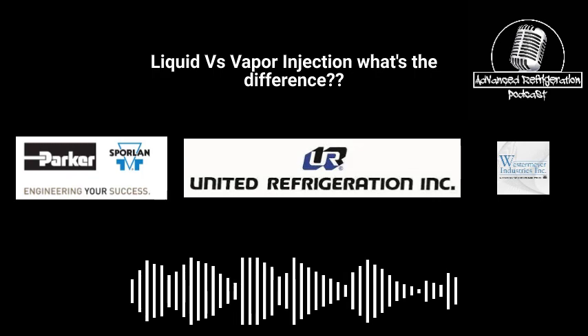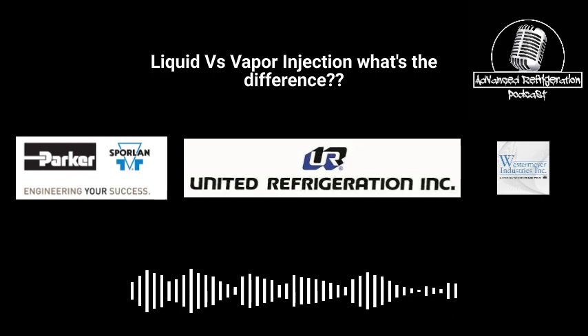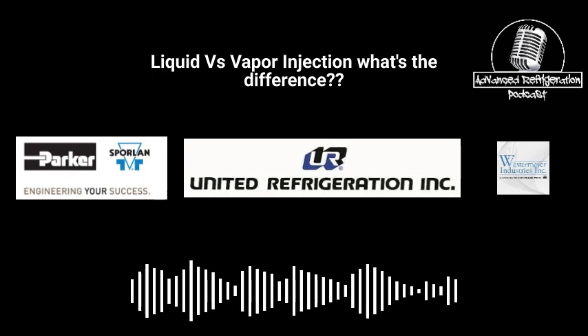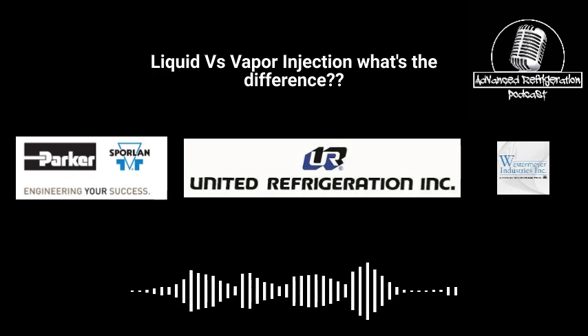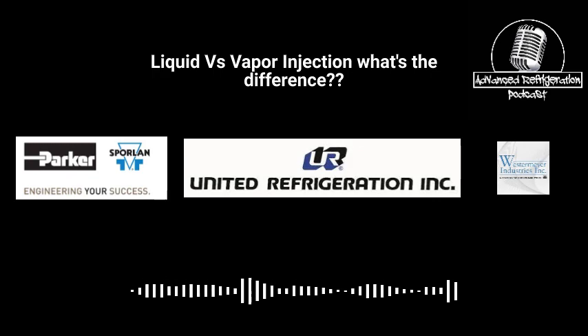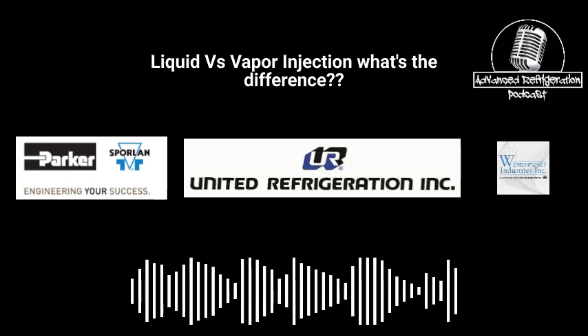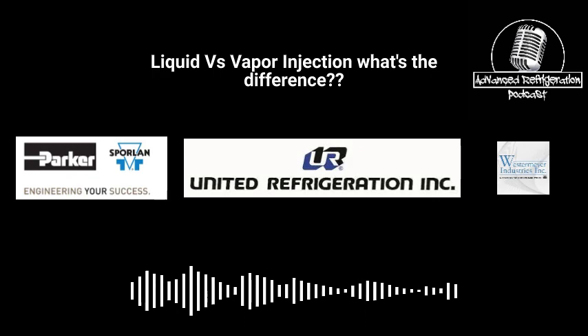So when you're having to rebuild that vapor injection, if you do not have an isolation line before that, isolate that whole compressor, pump it completely down to atmosphere, and then rebuild it, because otherwise you're not going to have a real fun time. It is hard to keep a solenoid cap down when there's 50 pounds there. Oh no, it wants to just blow right out of your hand. So I don't recommend it at all.